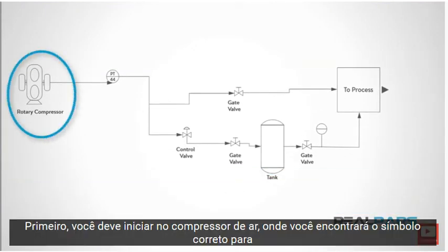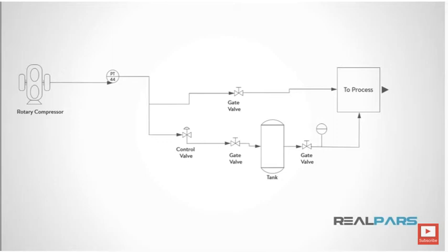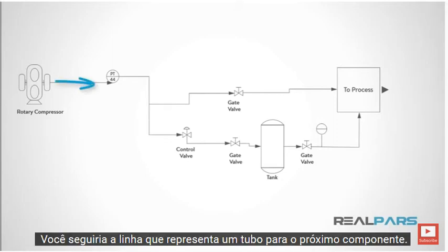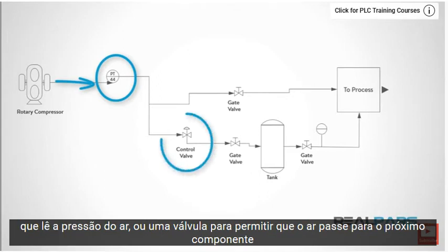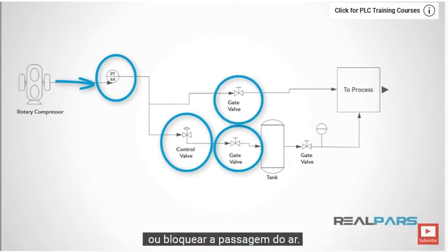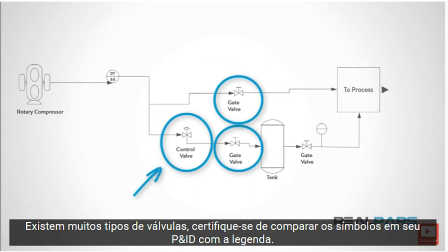First, you should start at the air compressor, which you'll find the correct symbol for on a legend of all symbols used. You would then follow the line, which represents a pipe, to the next component. In most cases, it will be some form of instrumentation, like a pressure transmitter or indicator that reads air pressure, or a valve to allow air to pass through to the next component or block the air from passing through. There are many types of valves, so be sure to compare the symbols on your P&ID to the legend.